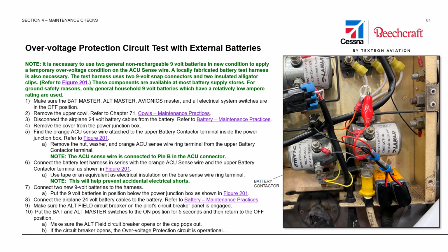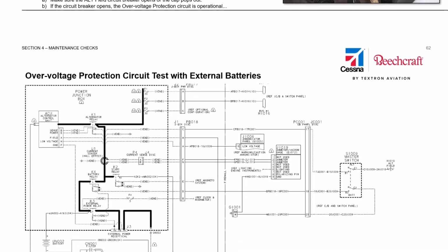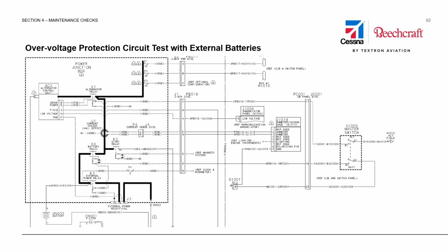This puts about 42 volts into the sense line and should cause the ACU to ground its power input wire, popping the 5-amp alternator circuit breaker. If this happens, the system is functioning normally. Let's look again at this test using the wiring diagram. The first thing to note is that the diagrams often show the sense wire tied to the alternator relay. This is not how Lamar actually builds the ACUs.